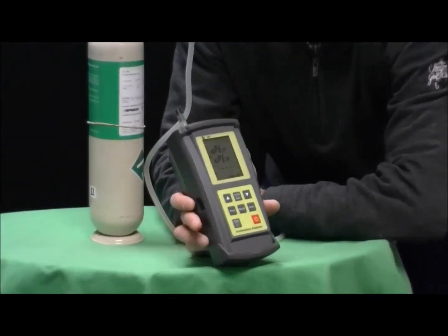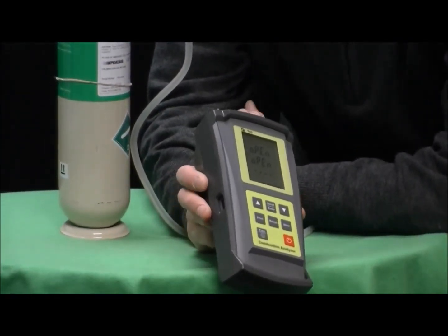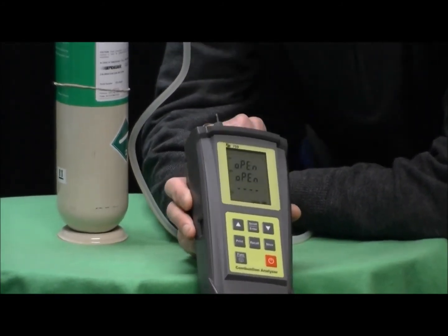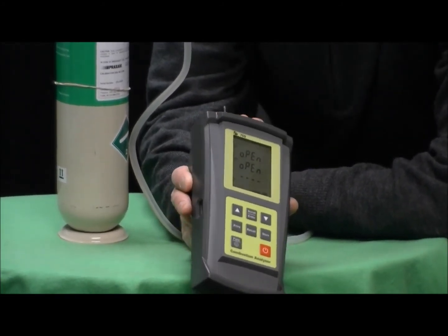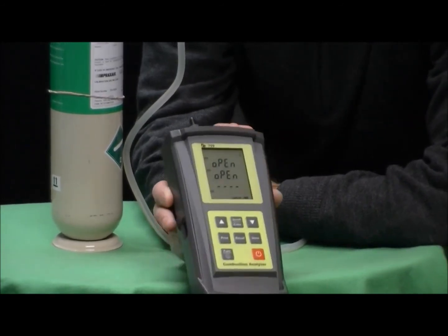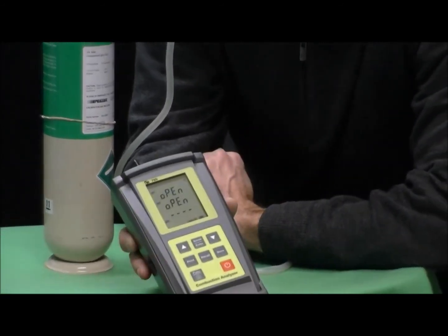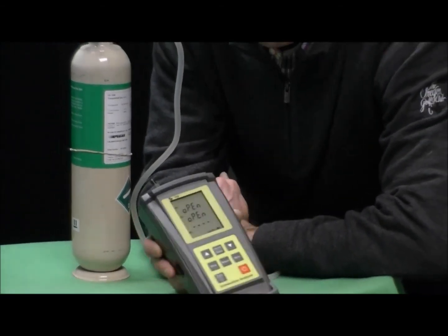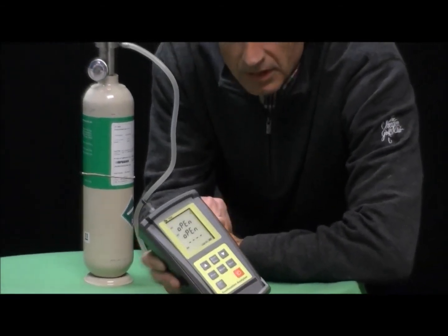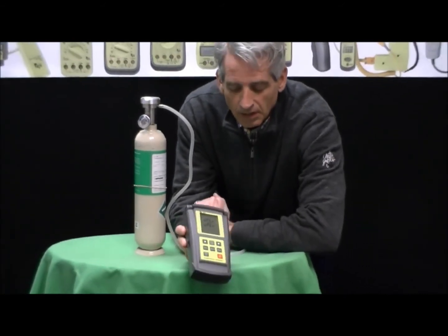million CO. And why that's important is when you look at the competitors, many of the competitors out there, they're selling units that have plus or minus 10 parts per million. I've also seen plus or minus 20 parts per million. So what that could mean is one of the competitors' analyzers is reading 0 when in actuality it could be 10 parts per million inside a living space, or it could be 20 parts per million inside a living space, and that still would be well within specification of their units.